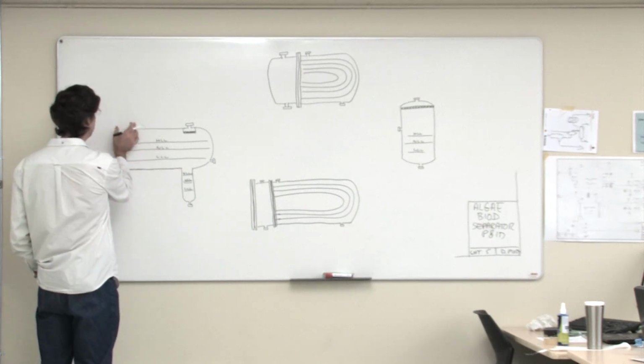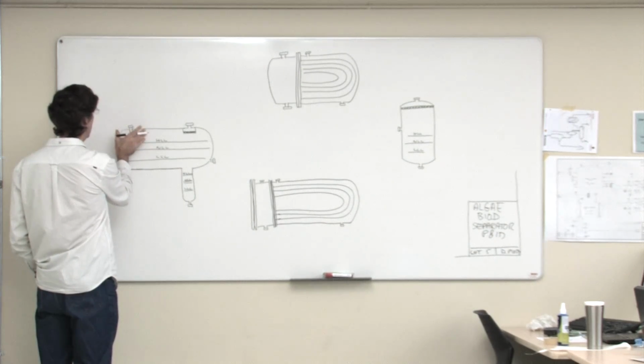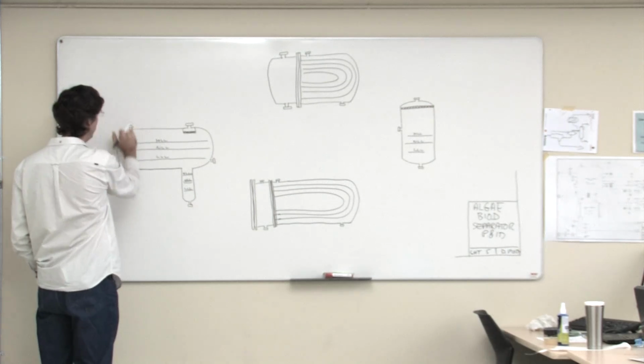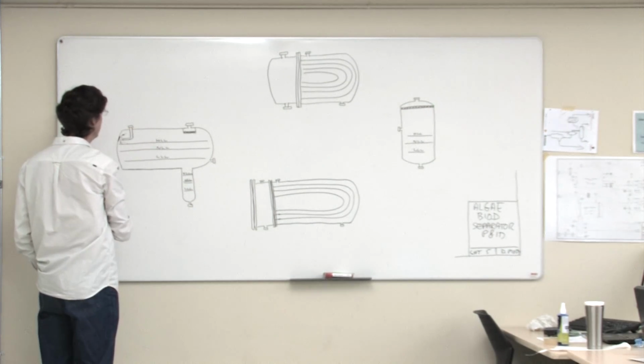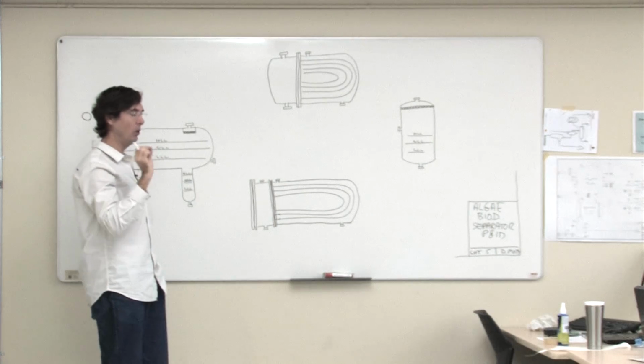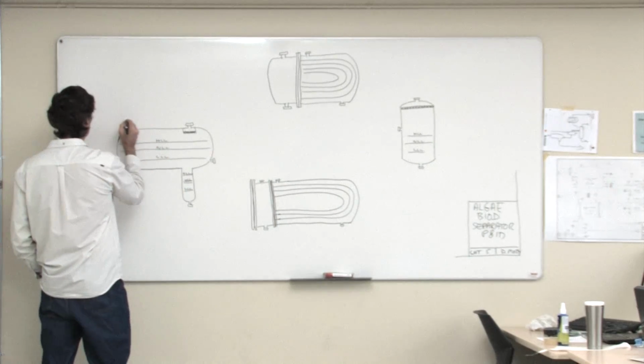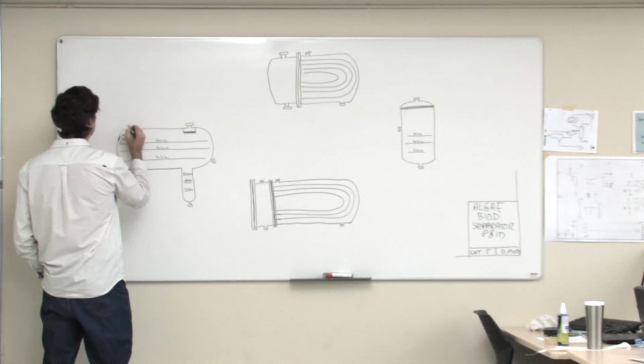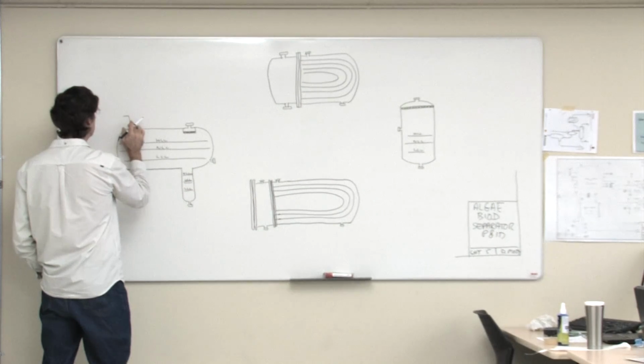I suspect there's a lot of pressure drop, so there's going to be a fair bit of flashing. We probably want to put that control valve as close to this vessel as we possibly can so we don't have a lot of two-phase flow in the lines. So if that's the case, I'm going to do it right here. We might even put it right up against the vessel, actually.